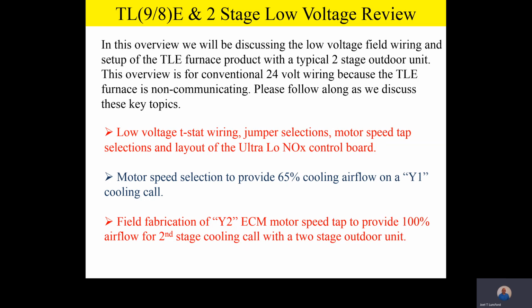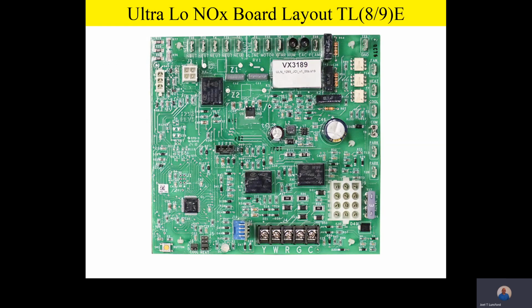So the first thing we'd like to do today is to go ahead and go over the ultra low NOx control board layout. And again, this control board will be found in both the TL8 and 9E product, the ultra low NOx product. So starting at the bottom of the board, this is where we're going to have our 24-volt thermostat hookup. It's very, very conventional. Y is going to be your cooling call. W will be your heating call. R is 24-volt hot. That's very conventional. G will be your fan call. And C is your 24-volt common.